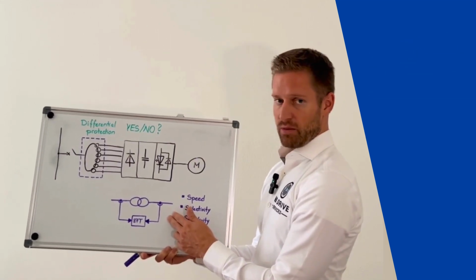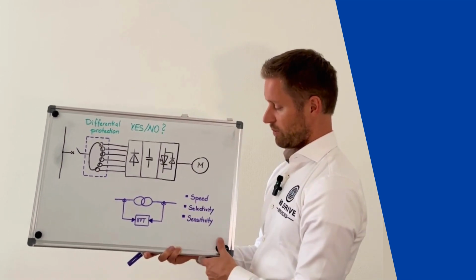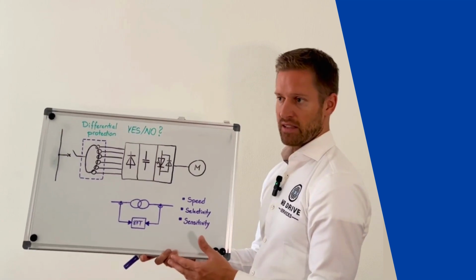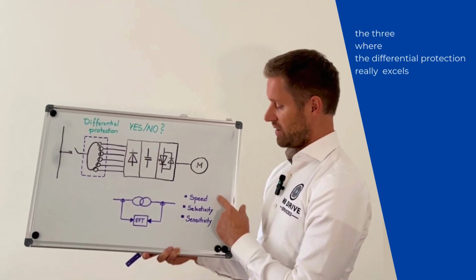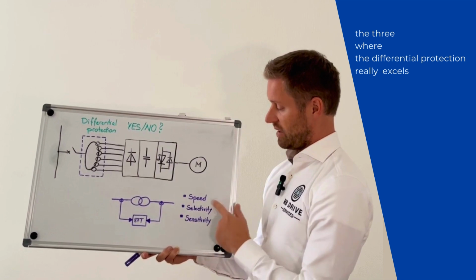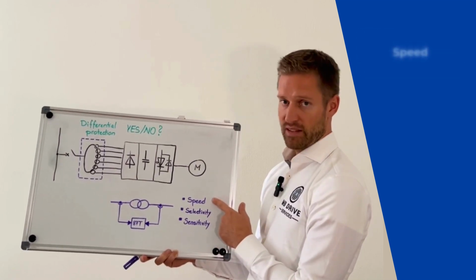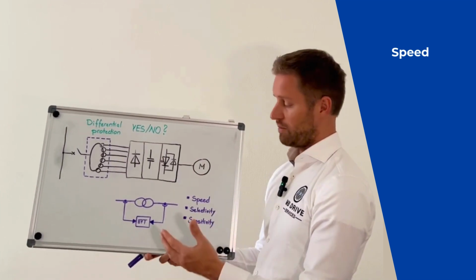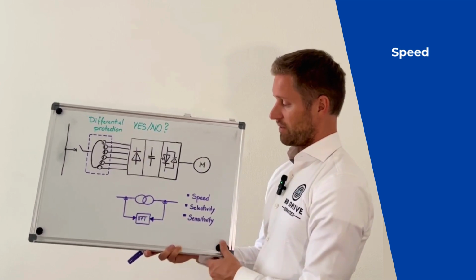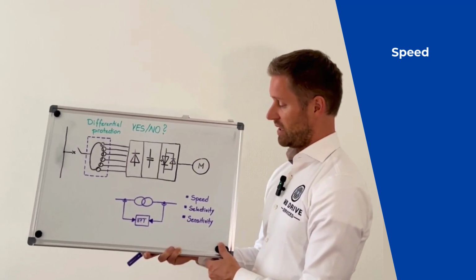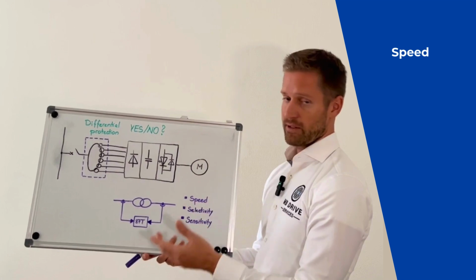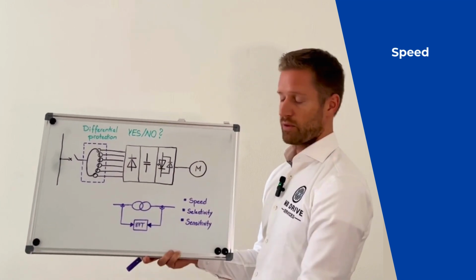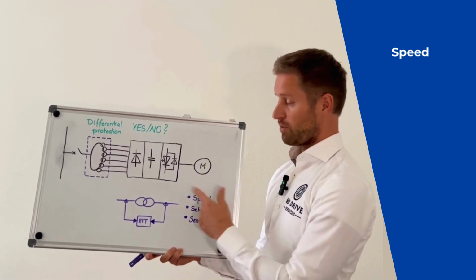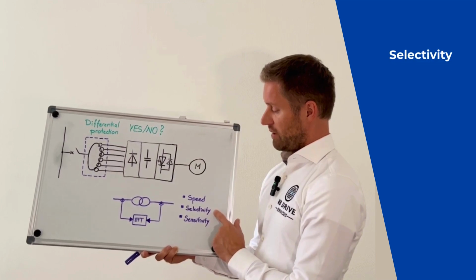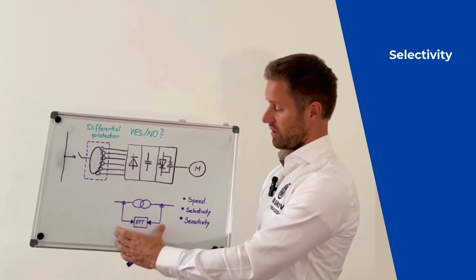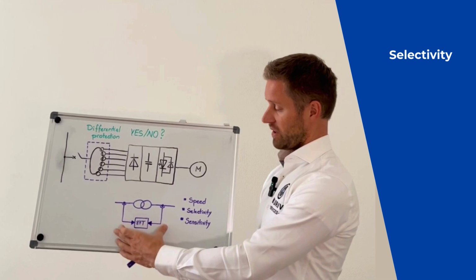Now, I mentioned that differential protection is appreciated due to some superior properties. Every protection scheme has certain objectives, and the three where differential protection really excels are listed here. One of them is speed, so this is basically the reaction time, how quickly the protection scheme reacts. The faster the reaction, the safer for the personnel because of the accumulated energy from the fault, and the smaller also the damage on the hardware.